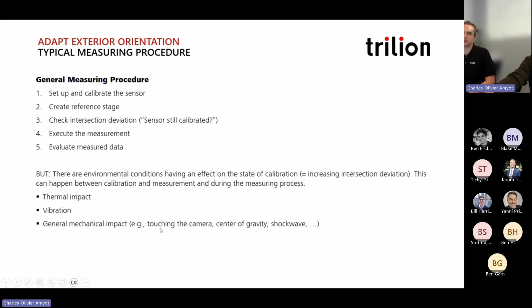Our general procedure in the past was setting up and calibrating the sensor, creating your reference stage, and checking your intersection deviation to see if the sensors were still calibrated. You'd do your tests and then analyze your data. But there could be other considerations that increase your intersection deviation, like thermal currents, thermal impacts, vibrations, and general mechanical impact—even moving the sensor, or somebody bumping into it, decalibrating it over time.